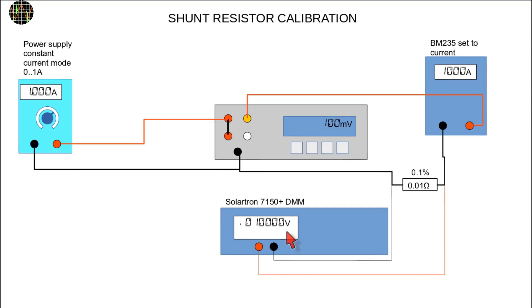With this method I can get a better accuracy than with the BM235 alone but of course you could use whatever reference instrument you have to verify that the current is exactly 1A.